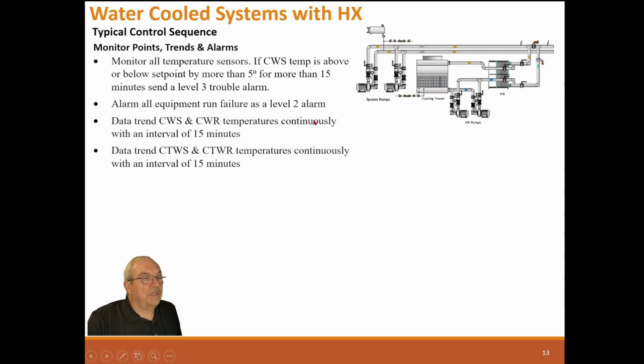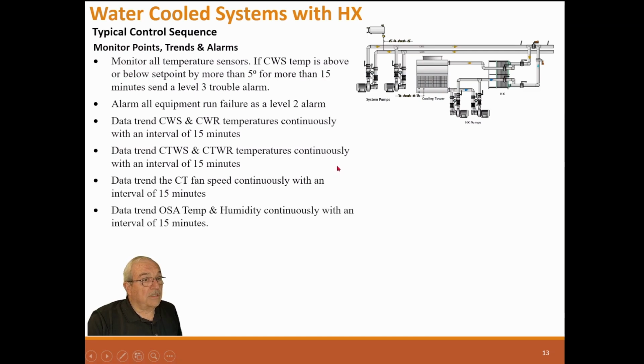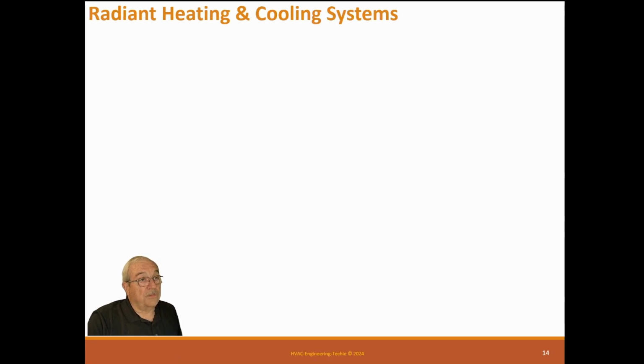Data trend the cooling tower water supply and the cooling tower water return temperatures every 15 minutes. Data trend the cooling tower fan speed continuously with an interval of 15 minutes. Data trend outside air temperature and humidity with an interval of 15 minutes. Data log run times of all motor assemblies for operators for maintenance, so they know when to maintain these motors, and it's got to be resettable in case they change a motor.